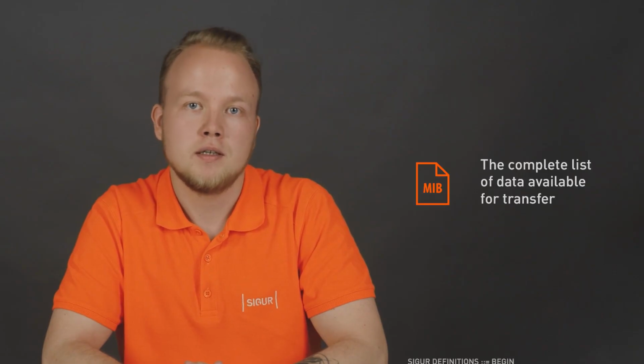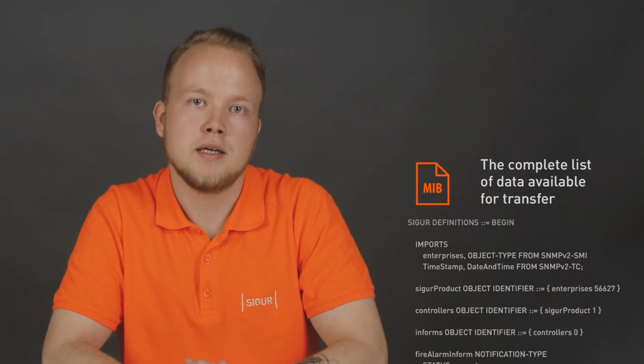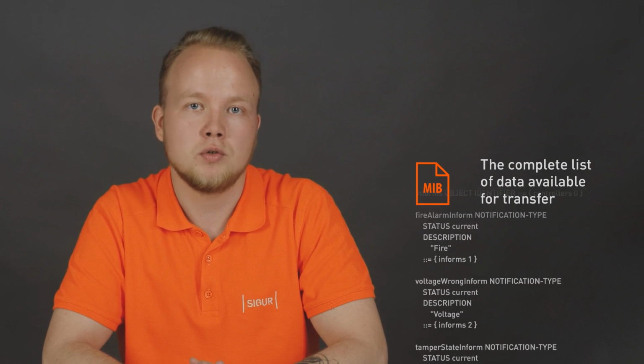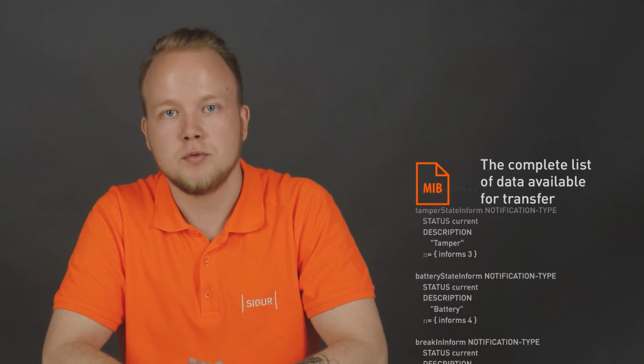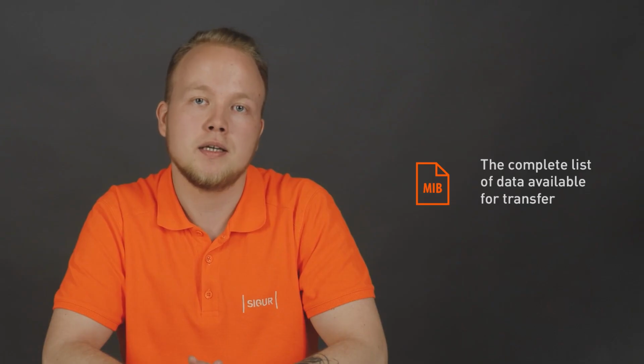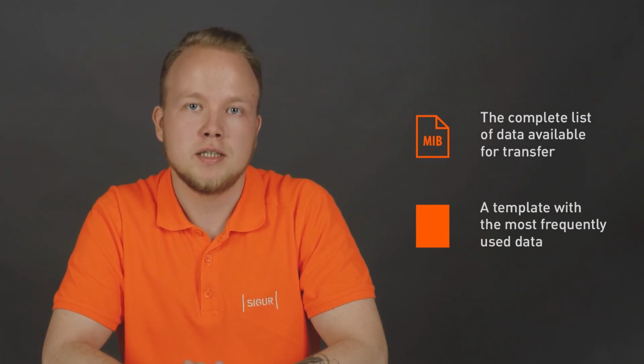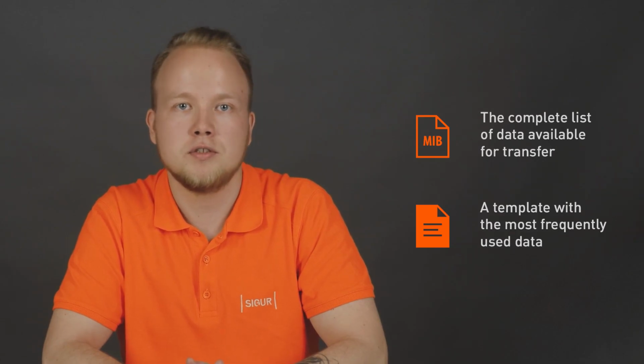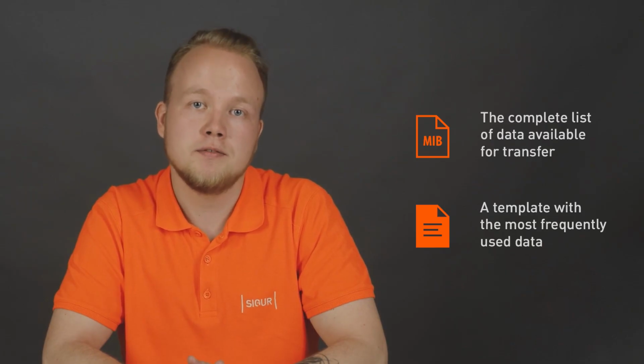It's important to note that this video is intended for experienced users and those who simply want to get acquainted with Sigur's capabilities and optimize the IT department's work regarding access control systems. For the first group, we prepared a special MIB file allowing more detailed template configuration, enabling the monitoring system to poll the controller about its relay's status, discrete inputs, OSDP connection status, readers, and much more. Additionally, we created a ready-made Sigur template including the main parameters that, in our opinion, will be of primary interest for monitoring. Using it in your system setup will save you a lot of time and make configuration much more convenient.